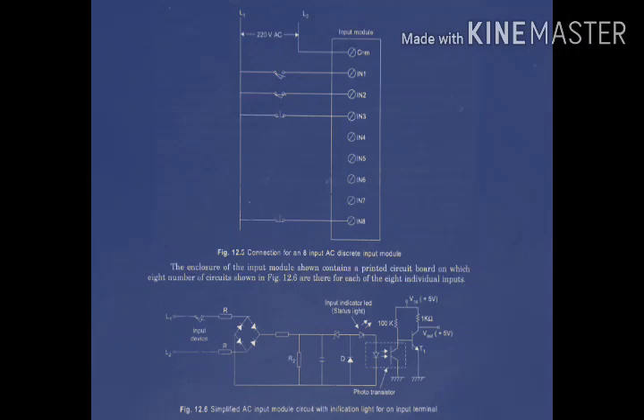Then there is the diode, again. There is a status LED which indicates what the status of the input is — whether the input is on. Then we use a phototransistor, which works as a switch. This is basically the electronic circuit. The role is to convert the AC 220V switch signal into the PLC, and then convert the circuit through to 5V.